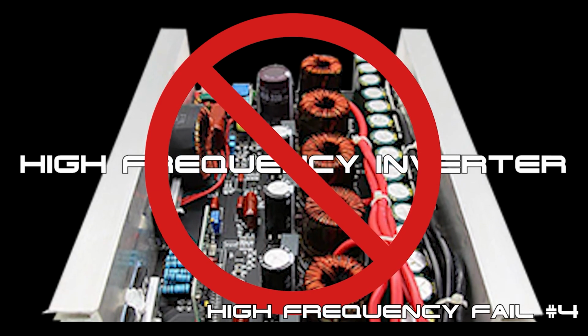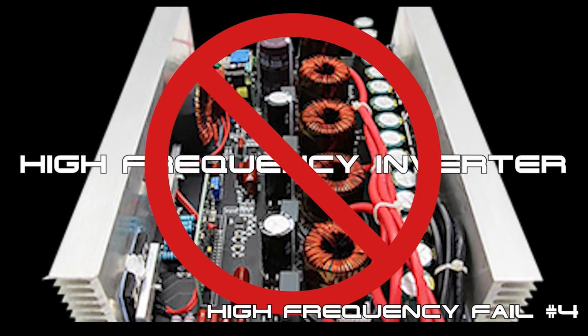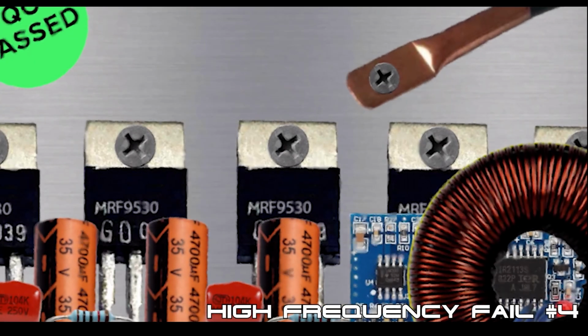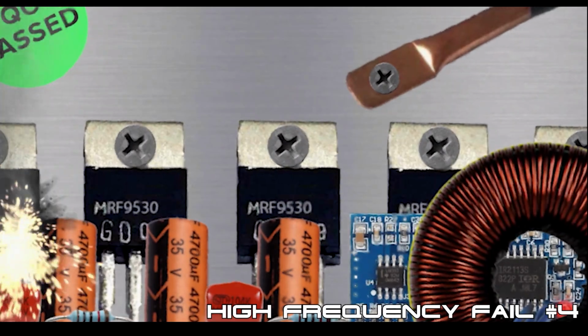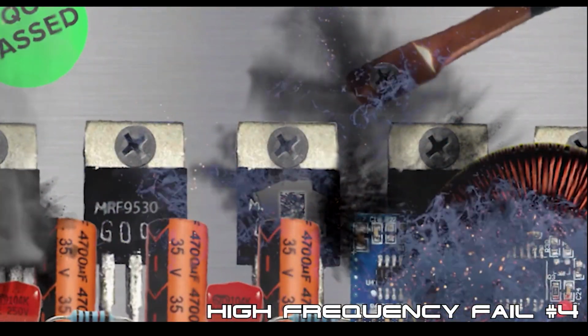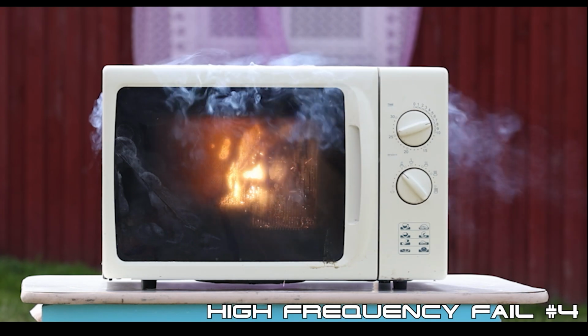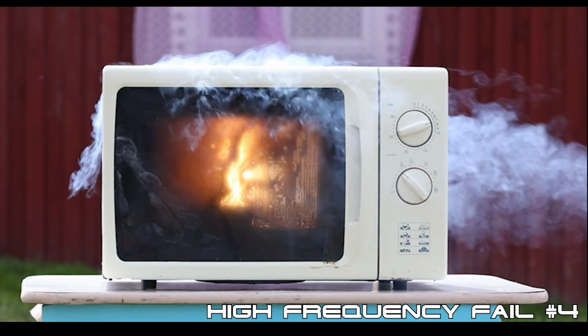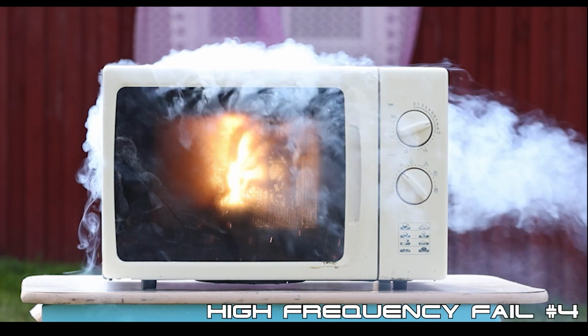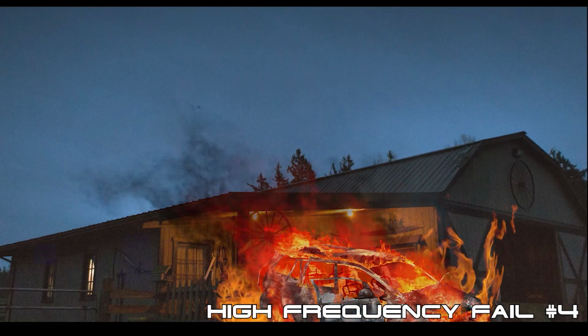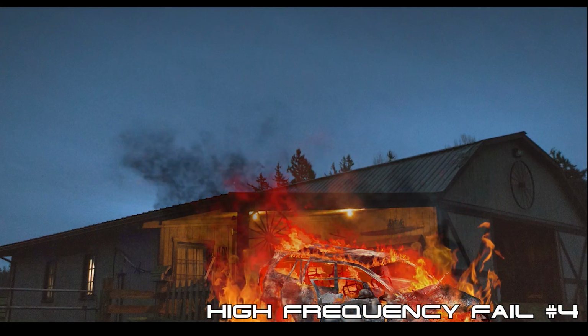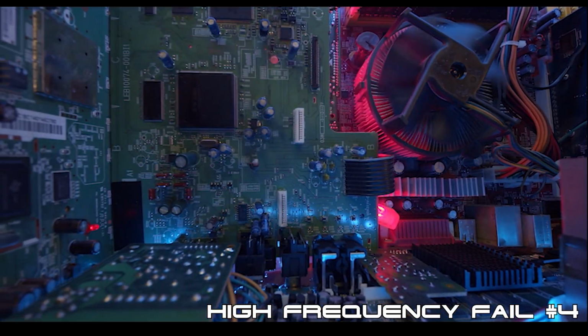Because there is no output transformer, if the output monitoring circuit were to fail, it would only take a single overheated MOSFET to short to ground, and high voltage, high current DC could pass through to your AC loads and set them on fire. In light of this, whatever you do, never attempt to charge an EV or power a computer with data that you care about losing with a high-frequency, transformerless inverter.